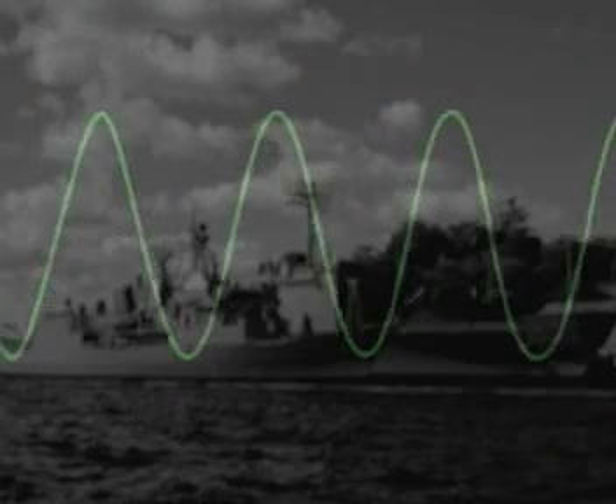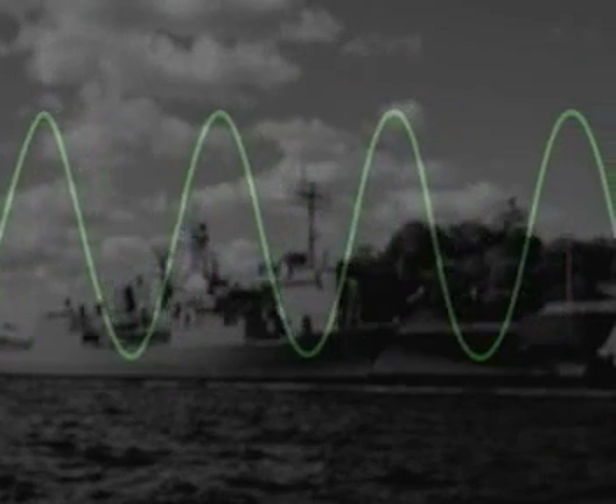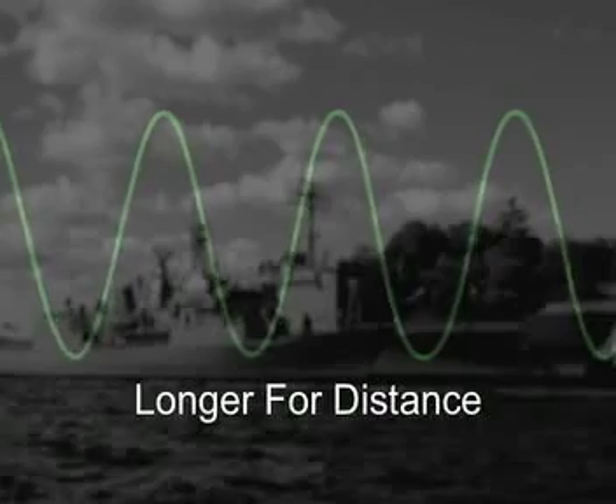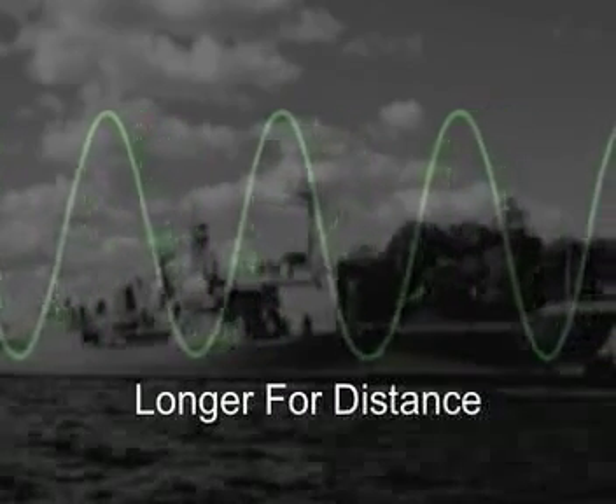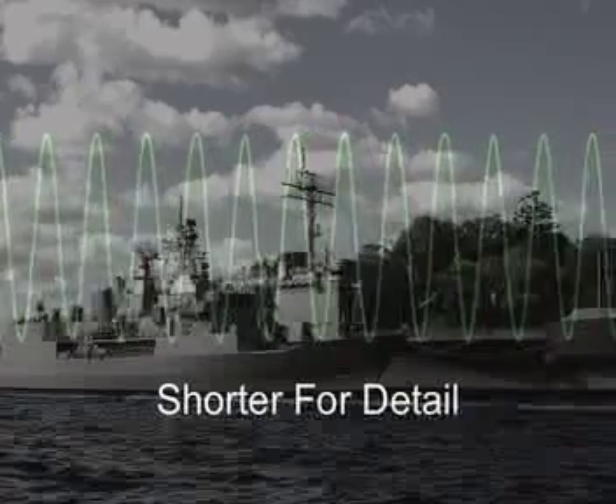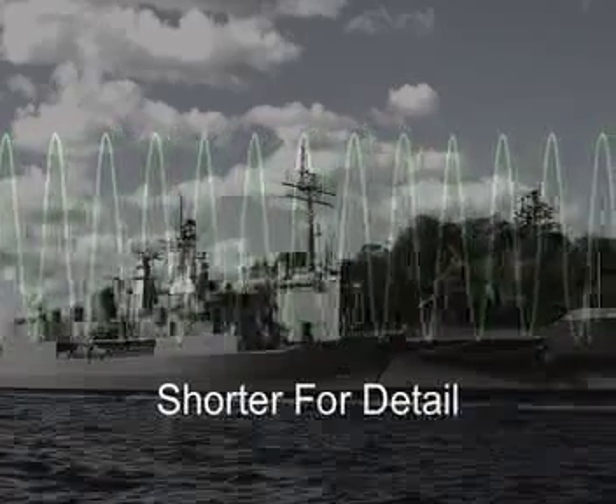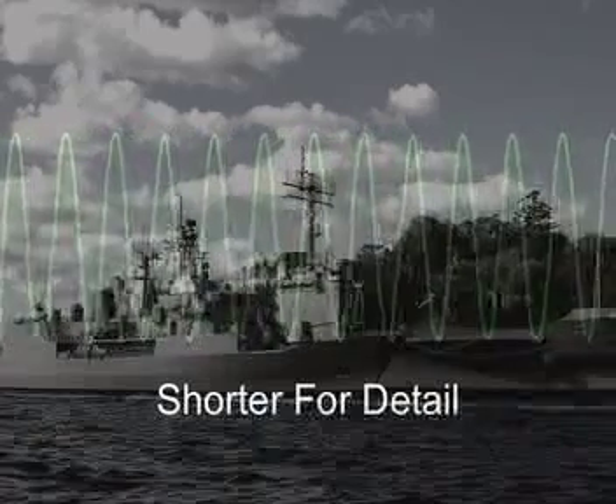The final step in calibrating the radar to your needs can be found in the pulse width setting control. This function modulates the actual amount of energy transmitted by the system. A longer pulse width transmits longer and therefore increases the range of your radar. A shorter pulse width transmits less energy, which sacrifices distance but increases the detail of the return image.